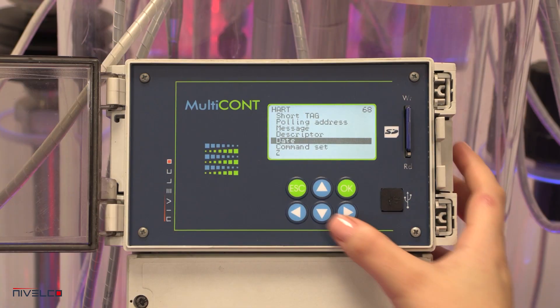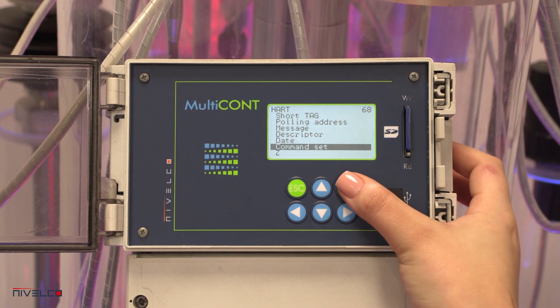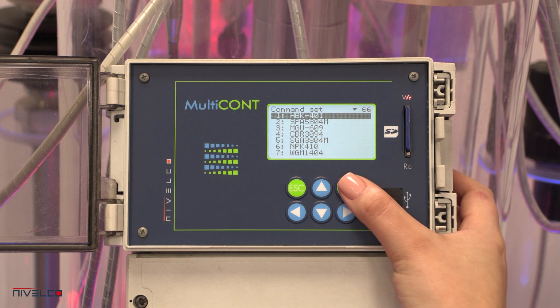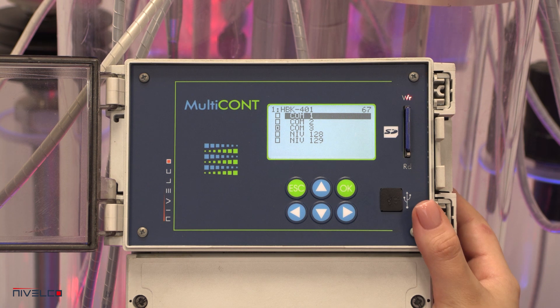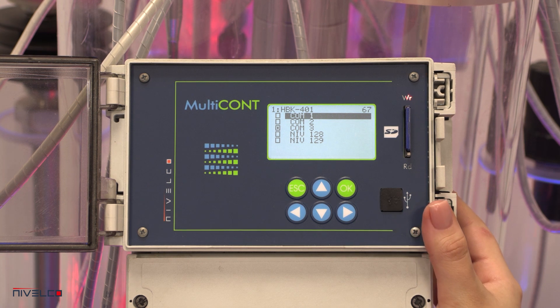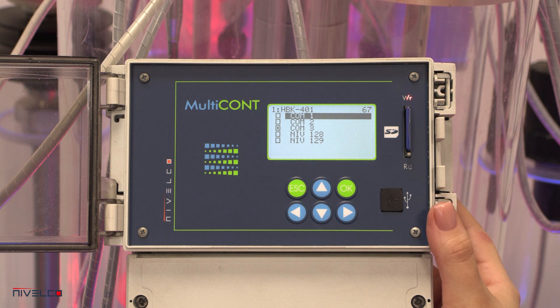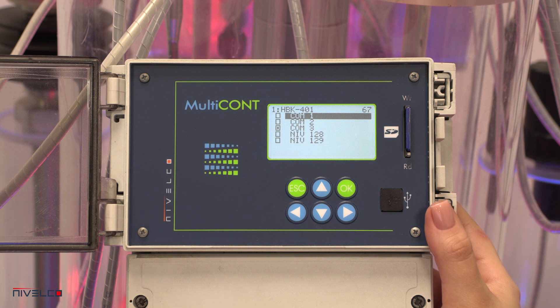The Multicont and the devices communicate using various commands. The Multicont sends a command containing the device's address, and the device replies with a standard response. Some of the commands are universal while others are device-specific. The appropriate commands are selected automatically based on the data required to control the display, relays, and current outputs.